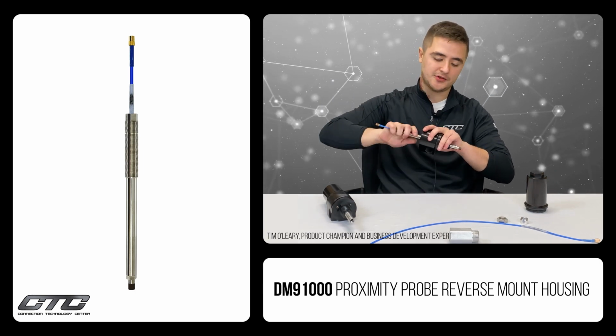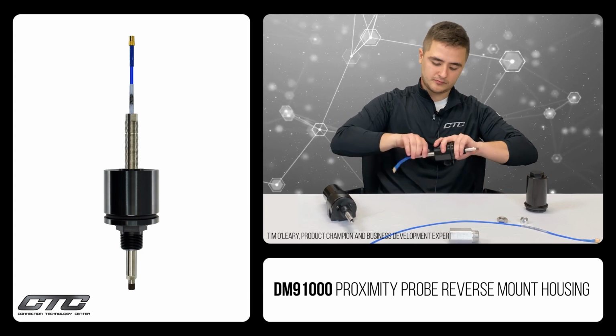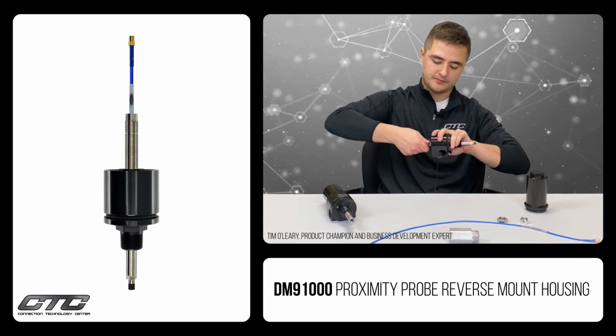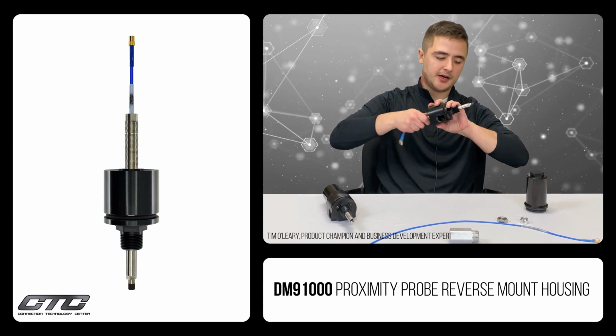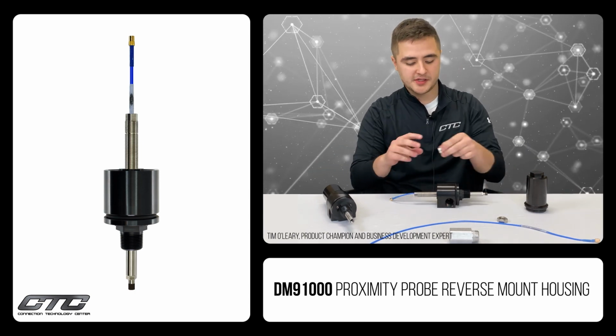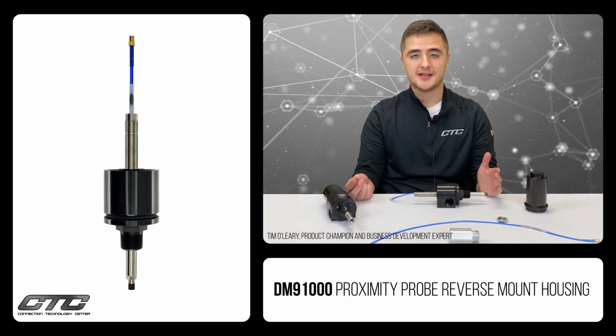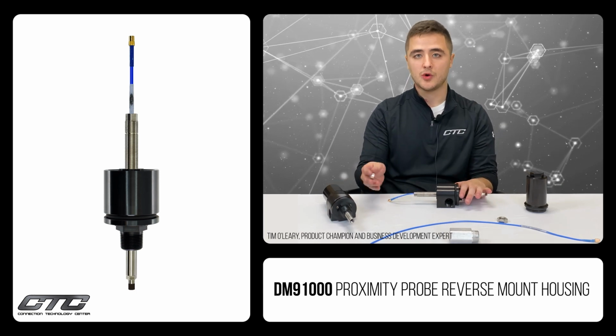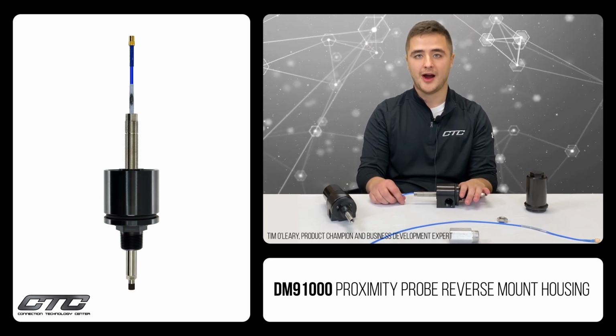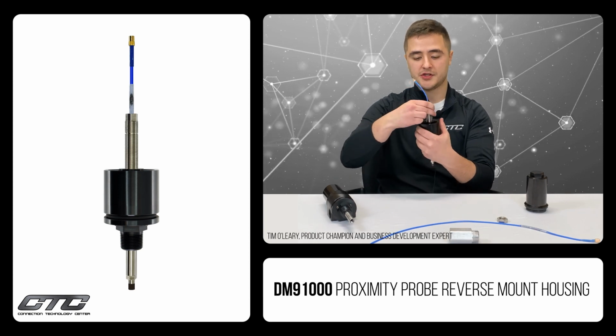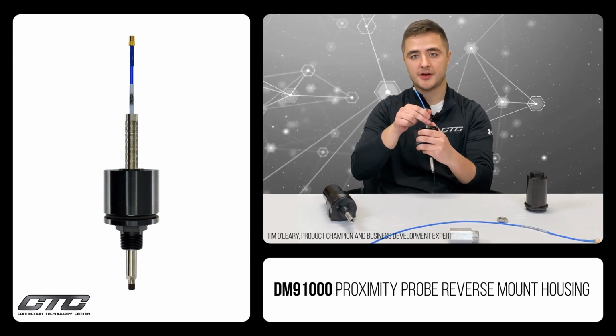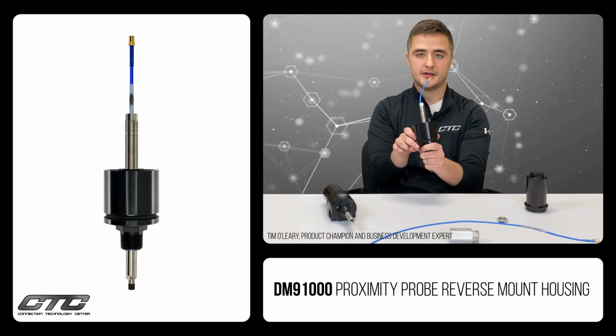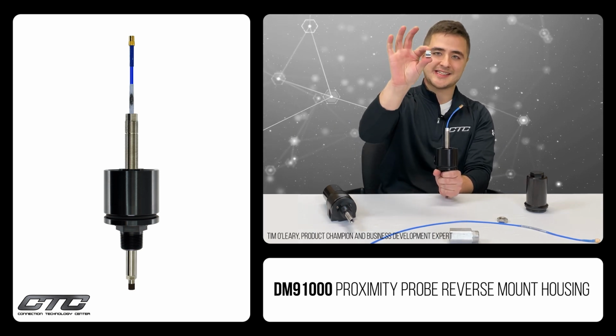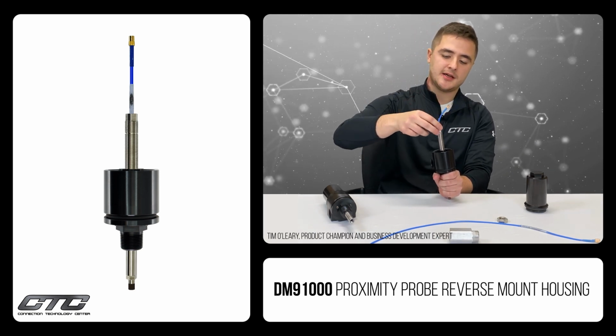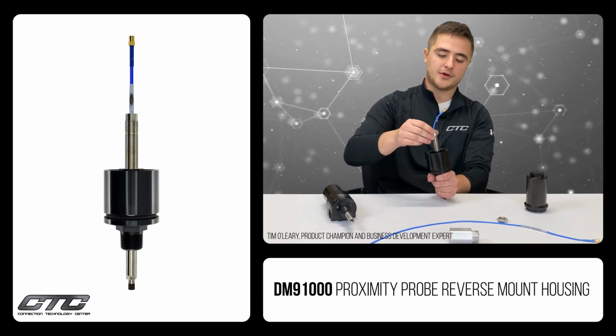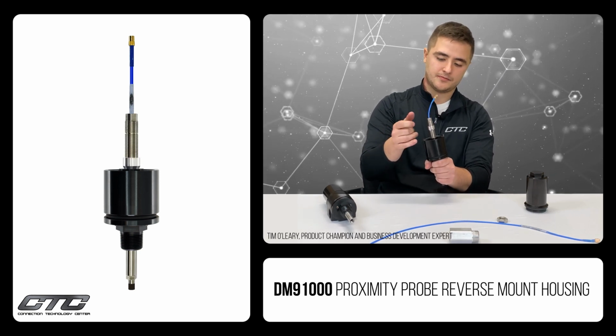Thread that into there. At this point, this is where you'll actually be setting the gap distance between the probe tip and your target material in the housing. So once you've adjusted the penetration depth of the sleeve to its desired area, you want to take the sleeve nut of the assembly next and thread that down over the sleeve, like so.